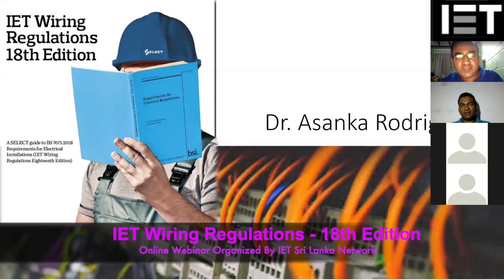Right, thank you. The next question is, what are the special major considerations for temporary installations apart from the permanent installations? Yeah, as I said, if you have a movable or temporary installation, it depends on the current rating. Even in the new regulation, it is made compulsory to have RCD protection for any movable installation. You have to provide the supply through a residual current device, an RCD, with 30 milliampere, if it is 30 ampere or lesser.